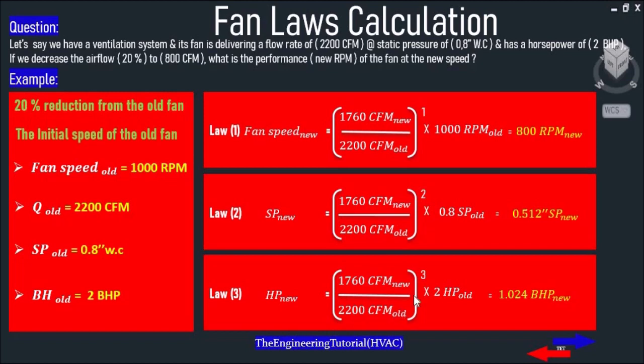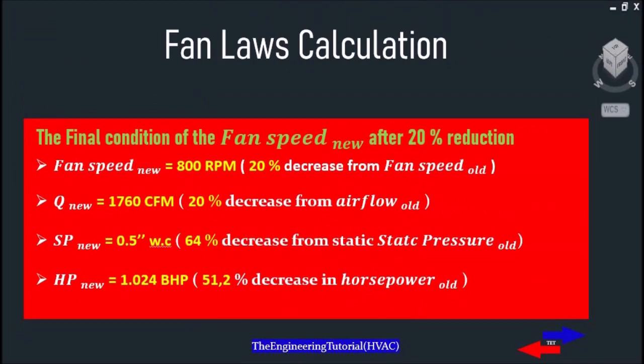Brake Horsepower New equals (1760 CFM New divided by 2200 CFM Old) cubed, multiplied by 2 horsepower old, which equals 1.024 brake horsepower new. As you can see, the horsepower has changed from 2 to 1.024.